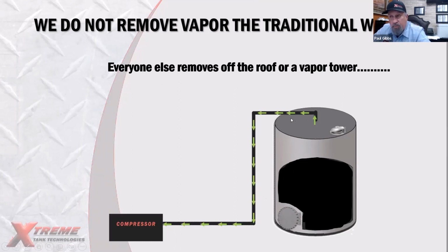What happens is you go to 4 ounces, your compressor comes on, and then these heavy molecules will flash, and you go to 13 ounces, and you leak for 30 seconds, 90 seconds, 120 seconds, whatever the time frame might be, until it releases itself back off.